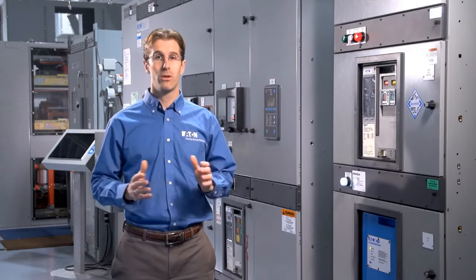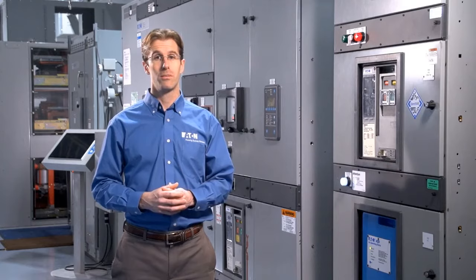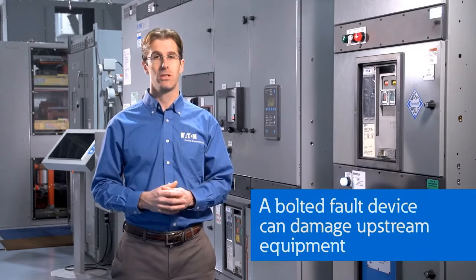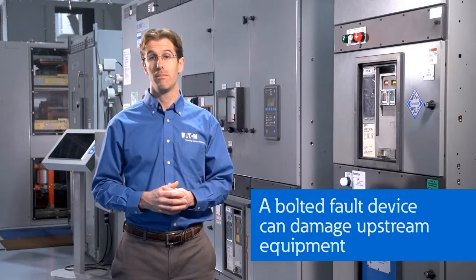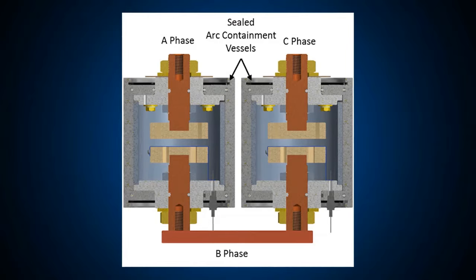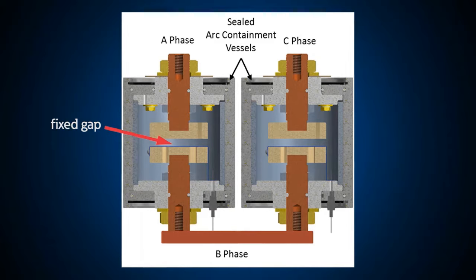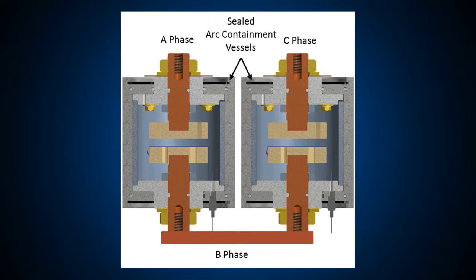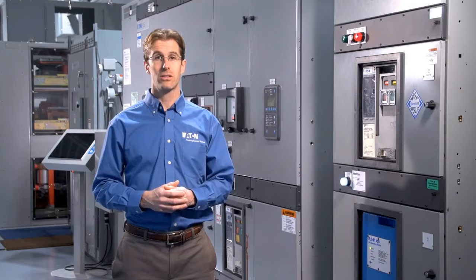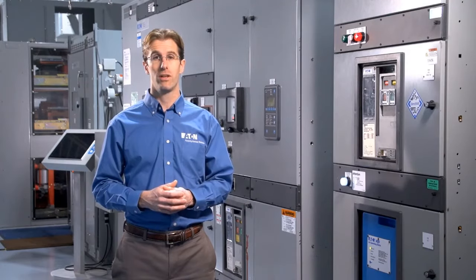But of course, we didn't want to create just another bolted fault device, because such devices run the risk of damaging the upstream power distribution equipment via the massive electromechanical forces that are created when they operate at full fault current. So instead, these tan contacts are actually fixed in place. The air gap between them doesn't change under any circumstances. Under normal operation of the switchgear, these contacts are far enough apart that there's no arcing across them. You can even high pot or dielectric test the equipment with the arc quenching device installed, and it will not cause the switchgear to fail the test.